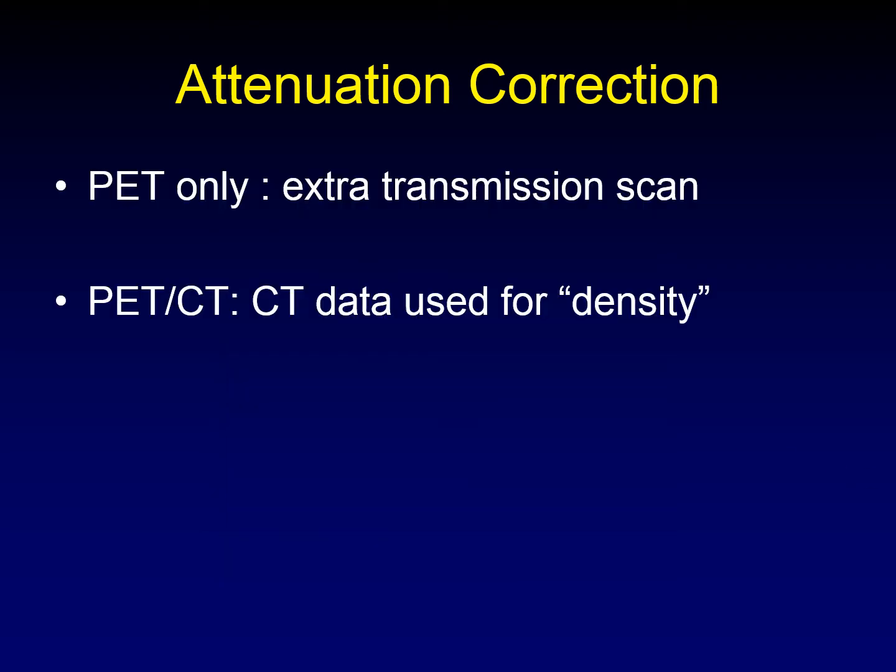There's more than one way to correct attenuation. When we only had PET, we used to do an extra transmission scan to figure out how dense the body was at different parts. Once we started using combined PET-CT, we could use the CT data to correct for different densities in the body. It turns out CT is a really good approximation for the attenuation that these high-energy photons undergo, so we can use the CT for our mathematical models.